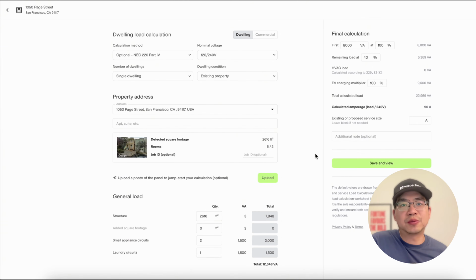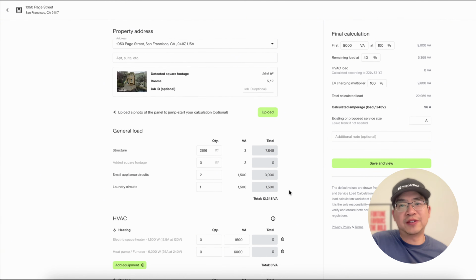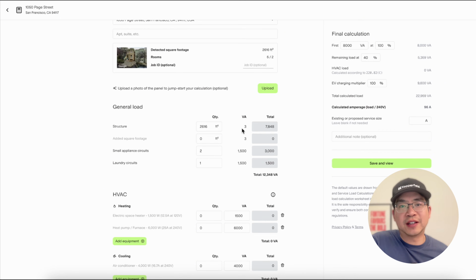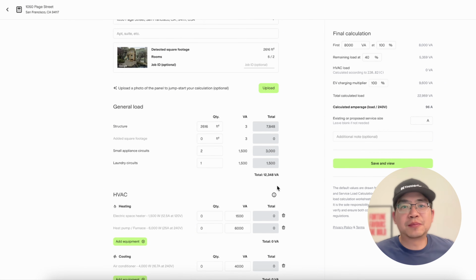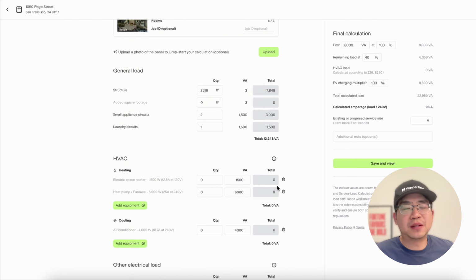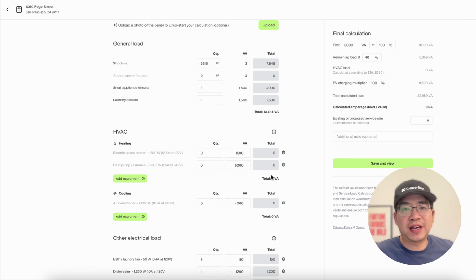So 3 times the 2,600 square feet is around 7,800 VA, and it looks like the calculator has got that accurately. Now we add in the small appliance circuits. The NEC has a minimum of 2 of these at 1,500 VA as well as the laundry circuit. Some homes might have more than the minimum, so factor it in if that's the case.